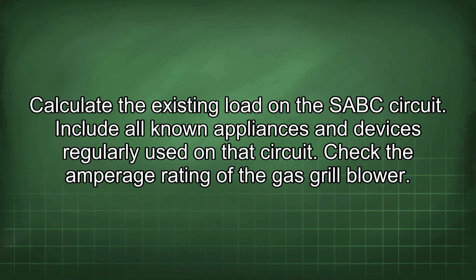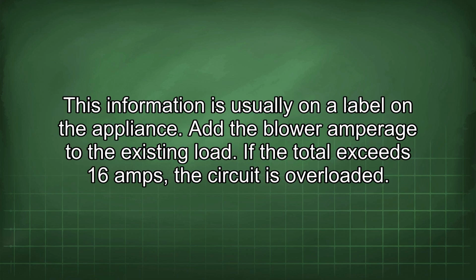Calculate the existing load on the SABC circuit. Include all known appliances and devices regularly used on that circuit. Check the amperage rating of the gas grill blower. This information is usually on a label on the appliance. Add the blower amperage to the existing load. If the total exceeds 16 amps, the circuit is overloaded.